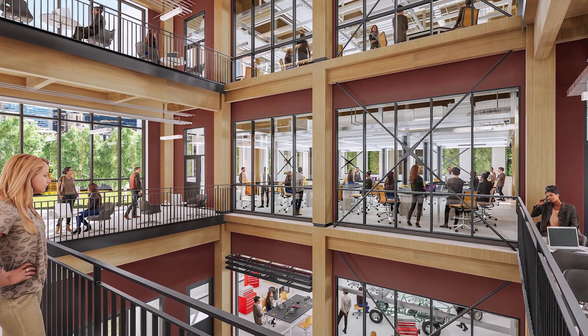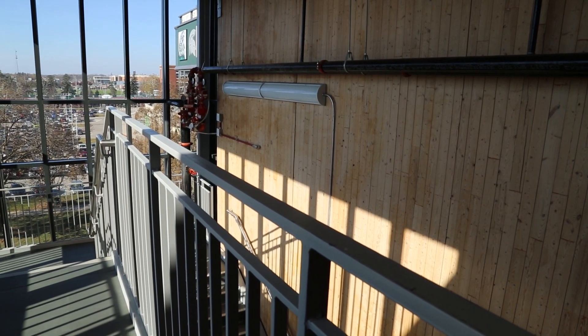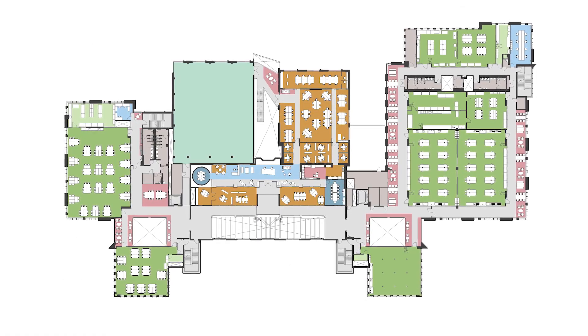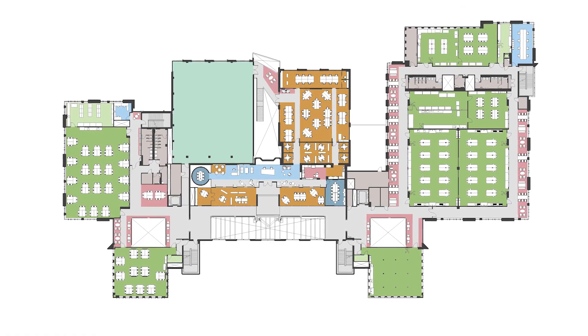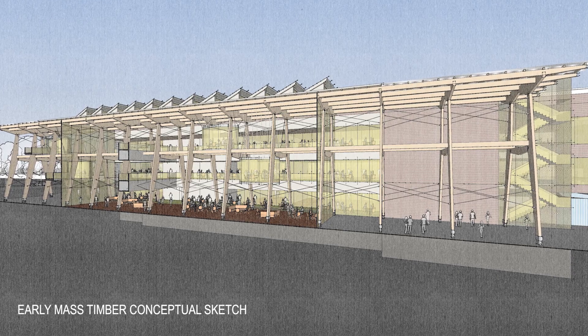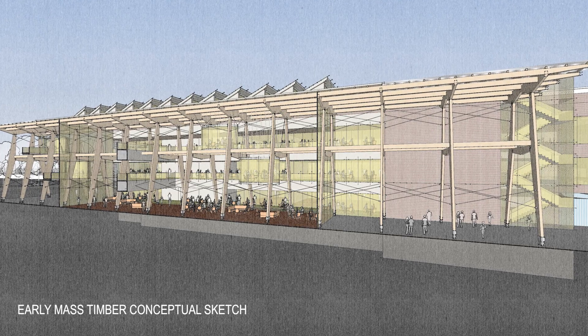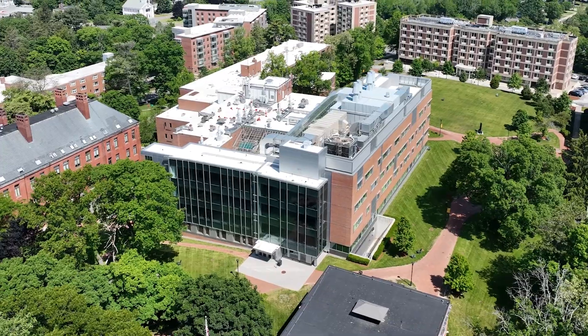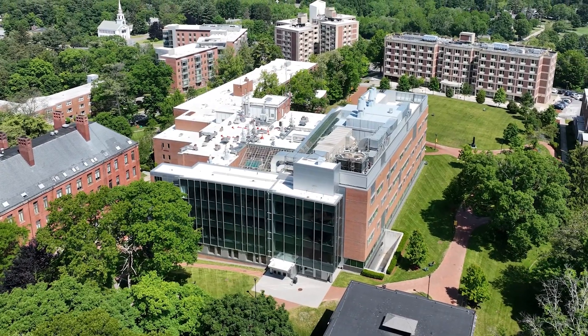Anytime we have higher occupant loads, we want to be closer to exits, have more exits, and have a shorter building — or provide more protection through construction type. If we want to go really tall or wide with a building, we need to make sure it's resilient to fire so that people have enough time to escape. Lab and life science buildings are just bigger than other spaces, to provide for both functionality and safety.